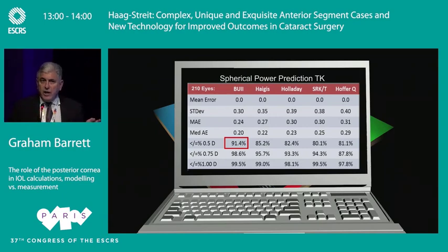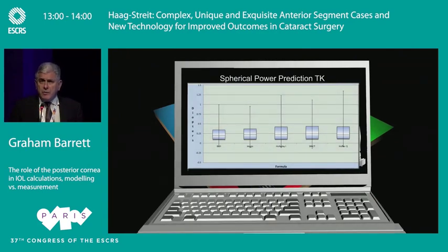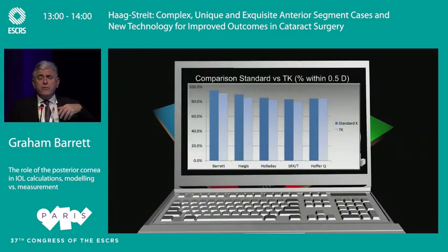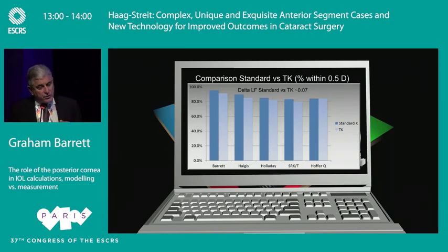This is with normal eyes, so that's a proviso. What's quite reassuring is that if you look at the optimized lens factor for standard K versus the optimized lens factor when the posterior cornea is measured, there's very little difference — only 0.07. So it's reassuring that you can use the same constants for both versions of the formulae.